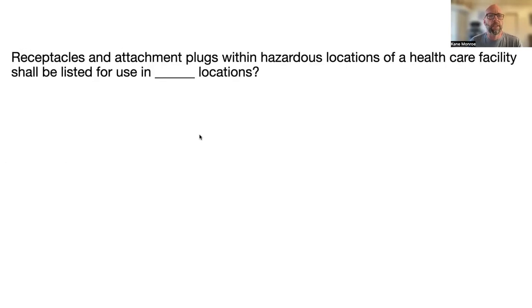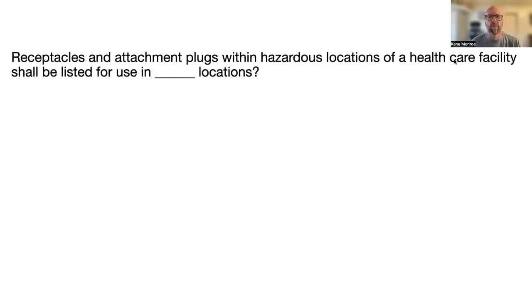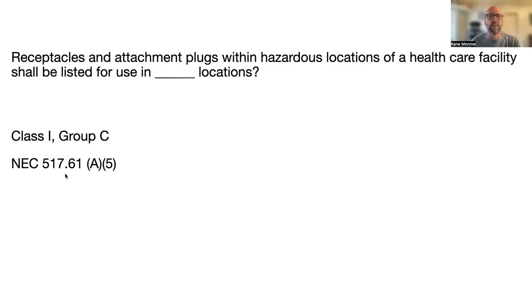Next question: receptacles and attachment plugs within a hazardous location of a health care facility shall be listed for use in blank locations. Health care facilities are covered in Article 517. Go to the keyword index, find 'health care facilities,' look for receptacle listings in hazardous locations, and the answer is Class I, Group C. That's found at NEC 517.61(A)(5) — highlight that.